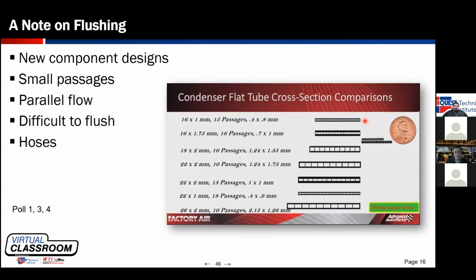All right, so the correct answer for that question is both. The RRR machine has to conform to J2843 or J3030, which defines the minimum performance standards and the methodology. And part of that standard, Technician B is correct. Every machine is going to require refrigerant identification, and if the refrigerant is not pure, the machine will not recover it. And then question 4, Brent.